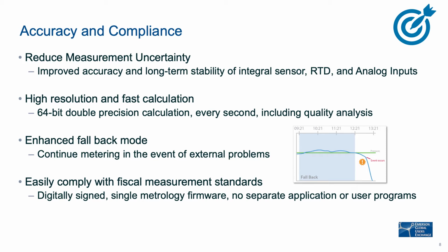We are using the latest Rosemount multivariable sensor 215, which has better accuracy performance in real process environment of high pressure and high temperature. The best-in-class temperature measurement done by using our onboard RTD input reduces the uncertainty by as much as 75%. Now, once the data is received inside the flow computer, it goes into calculation algorithm.